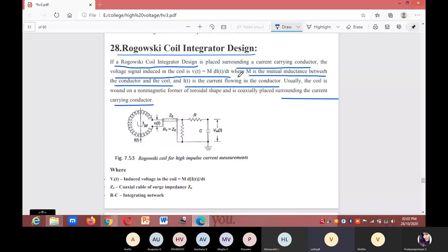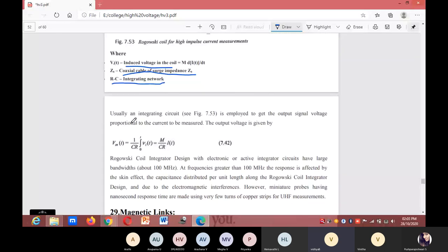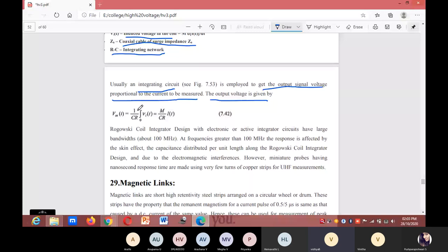Here V_i(t) is the induced voltage in the coil, Z₀ is the coaxial cable surge impedance, and R and C form the integrating network. An integrating circuit is employed to get the output signal voltage proportional to the current. The output voltage is V_m(t) = (1/CR) · integral from 0 to t of V_i(t) dt = M/(CR) · i(t).